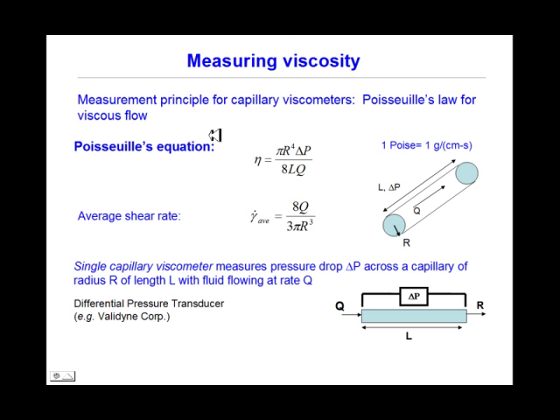To measure viscosity, we use a very simple principle and apply Poiseuille's Law for viscous flow. A single capillary viscometer is used, which measures pressure drop across a capillary of radius r and length l with fluid flowing at a specific rate.